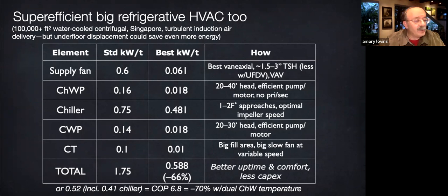Now the chillers have optimized impeller speed in their compressor. That doesn't cost extra. One gear ratio costs the same as another. You just need to specify it properly. And he uses very close approach temperatures, often around 1 Fahrenheit degree, because copper is cheaper than kilowatt hours. His cooling towers, typically Japanese Shinwa, save 90% of their energy by being specified big, squat, and fat, with big, slow fans rather than small, fast fans. Again, basic physics. And of course, all the cooling towers are dispatched in parallel at variable speed.